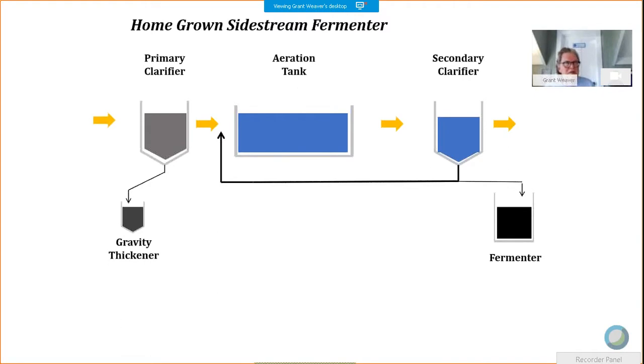If it's an aerated sludge digester and I can still meet all my sludge rules without aerating it all the time, then I'm going to cycle the air so that it's off most all the time. Maybe just turn it on while I'm dewatering or supernating the contents. If I do that, or if I have another vessel that I can use, maybe I'll put some sludge in there and let it sit long enough to go septic.